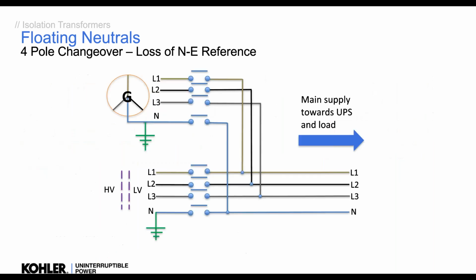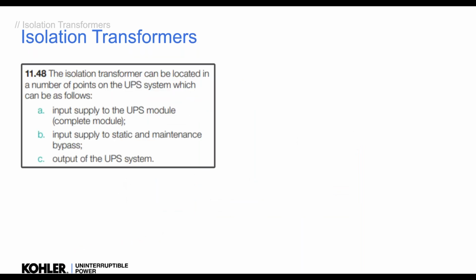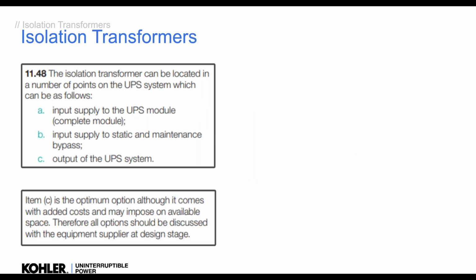Okay, we are trying to overcome the problem of a 4-pole changeover. Okay, and this is where we have a 4-pole changeover on one supply, typically over to a second supply being the generator. It could be 2 mains transformers that we're switching between. Okay, and we are worried that we're going to lose that neutral earth for that period of time. Okay, so the HTM suggests that we should have an isolation transformer either on the input to the whole UPS, input supplied to the bypass, the maintenance bypass, or on the output.